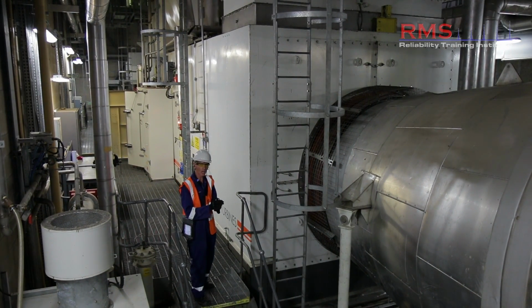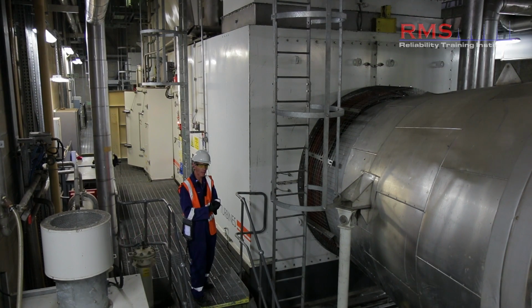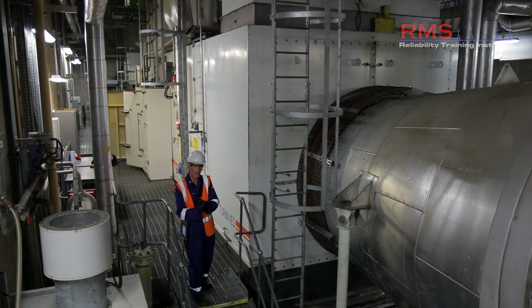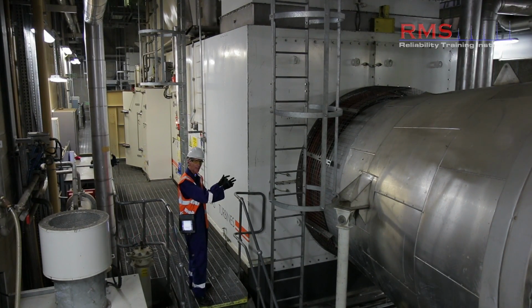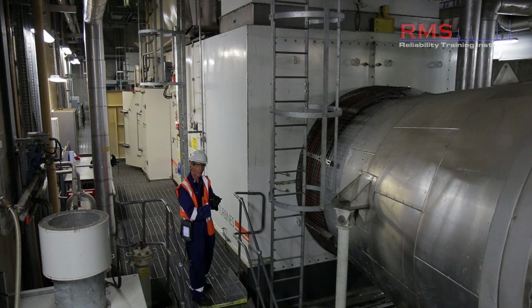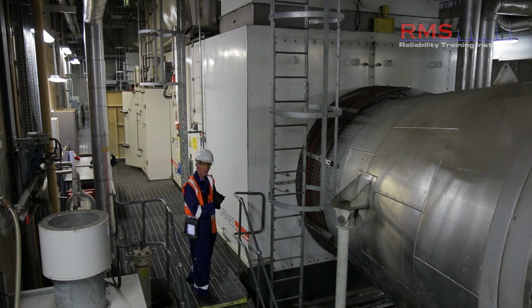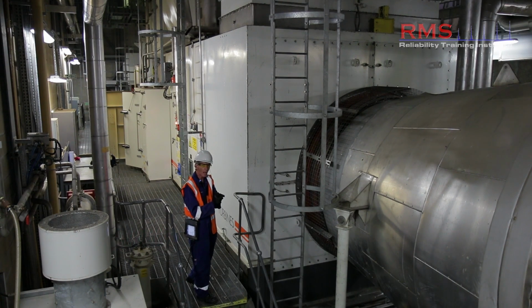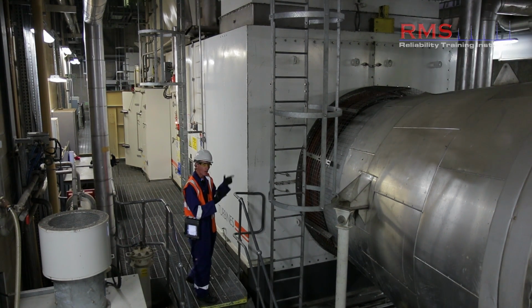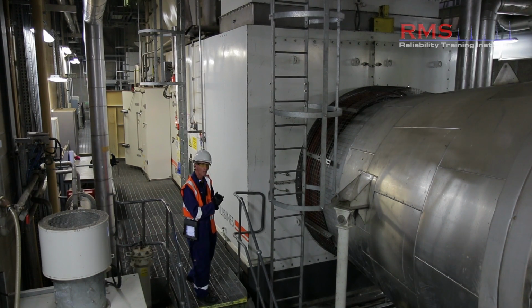Okay, so here we are alongside the 45 megawatt gas turbine referred to earlier. The power turbine end does about 10,200 RPM. The compressor end does about 3,500 RPM. And via a gearbox that reduces down to 1,500 RPM. And the gearbox obviously drives out to the generator at 1,500 RPM.